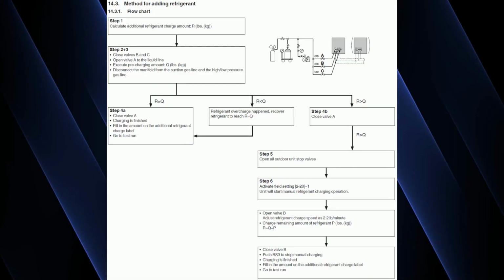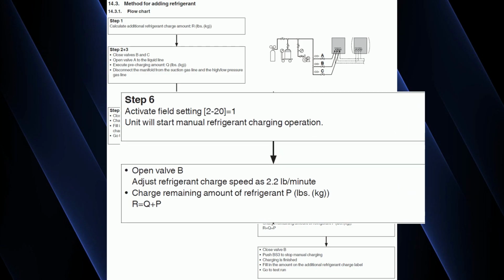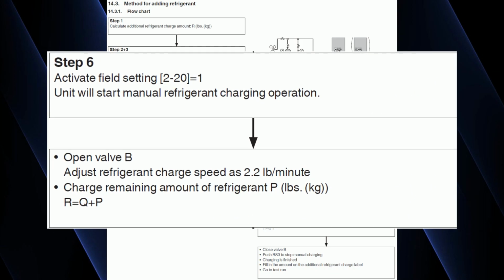You don't want to wash out the bearings. You don't want to wash that oil out from the compressor. So you need to make sure that you are metering the amount of refrigerant you're adding as the system's running and pulling it in. We typically just call this bleeding the refrigerant into the system. There is a specific rate you need to stay under, and that rate is stay under 2 pounds per minute. So as you're adding the refrigerant, you're watching the scale, you need to make sure that you are not adding more than 2 pounds per minute, if that makes sense.